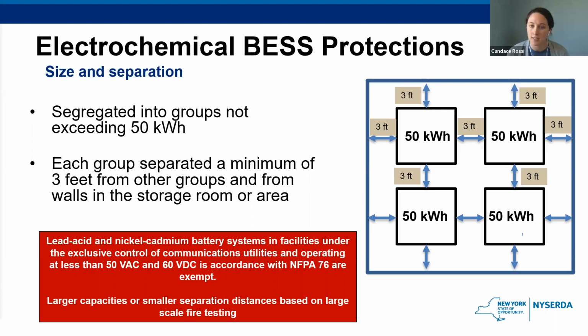So here is the size and separation requirement. Grouping of energy storage systems to a maximum of 50 kilowatt hours is there to reduce the fire load of a group or a rack. This grouping does not apply to remote outdoor installations. It does, however, apply to walk-in containers or cabinets that are outdoor and near other exposures. Walk-in units that are near exposures, while they need spacing between groups, do not need spacing between the wall of the walk-in unit. It also applies to energy storage systems that are in some rooms or areas that are indoor.